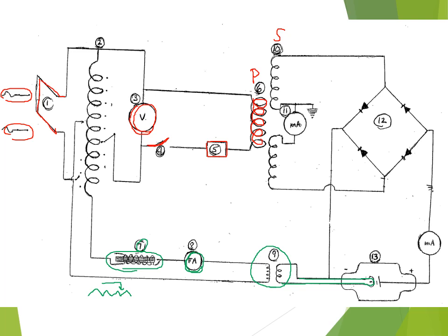The last parts that we have are number 10, 11, and 12. Number 10 is the secondary coil of that high voltage transformer, where we're going to have kilovoltage and milliamps. And that's why at number 11 we have a milliammeter, because we're going to measure tube current, which is the current going across the X-ray tube, and that's going to be in milliamps. Number 12 are the rectifiers, and we have four rectifiers. If we have four rectifiers, that means we have a full wave rectified unit. And then finally we have the X-ray tube at the bottom.